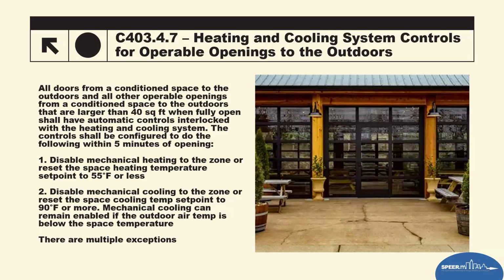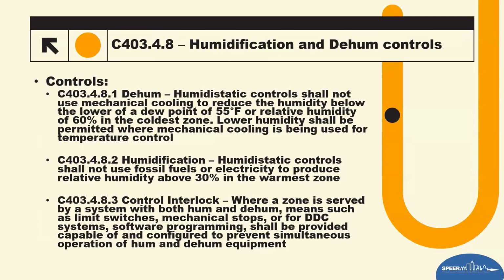So if the operable door or opening is larger than 40 square feet, which is what we see here, when that system is running and the door is open, it responds within 5 minutes. It will adjust the thermostat. If it's heating, it goes down to 55 degrees. If it's cooling, it goes up to 90 degrees. Cooling can remain on if the outdoor temperature is lower than the indoor temperature, allowing for free cooling. Basically, it's running, but it's cool outside like it is today. There are multiple exceptions for that, such as healthcare facilities and certain industrial uses. The simple idea here is that if the building is open to the outside, the HVAC shouldn't be fighting against the outdoor weather. So that's being addressed and reclarified in the code from time to time.